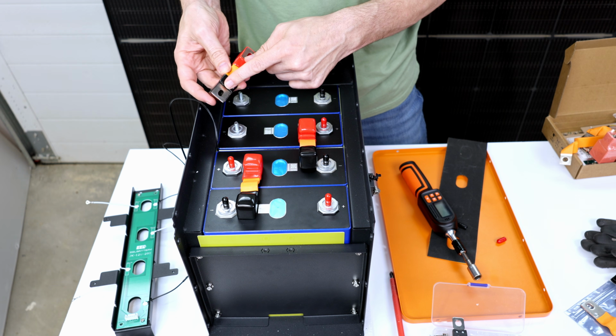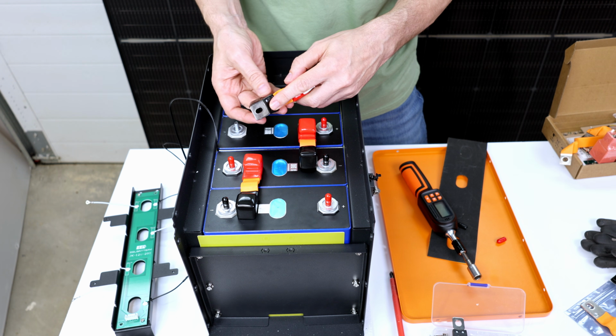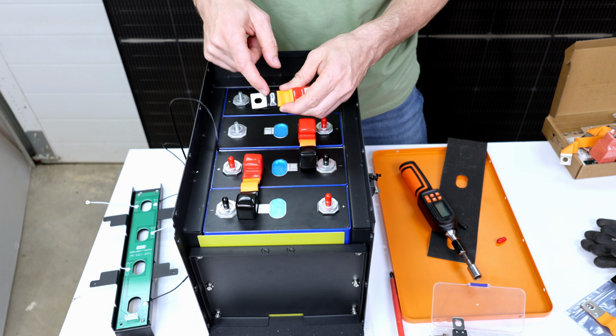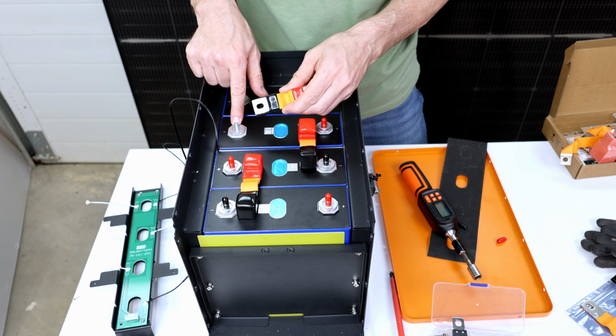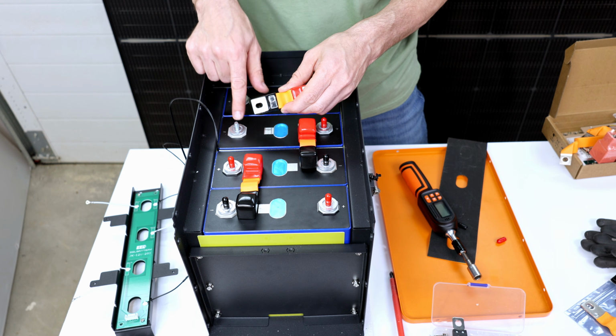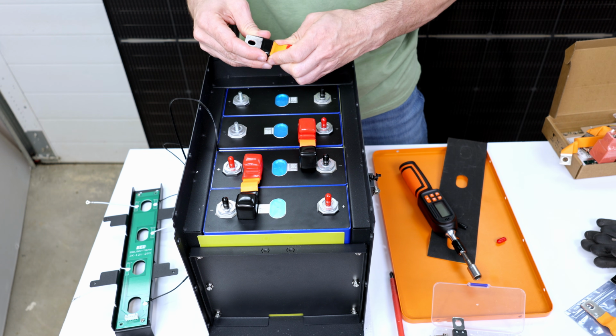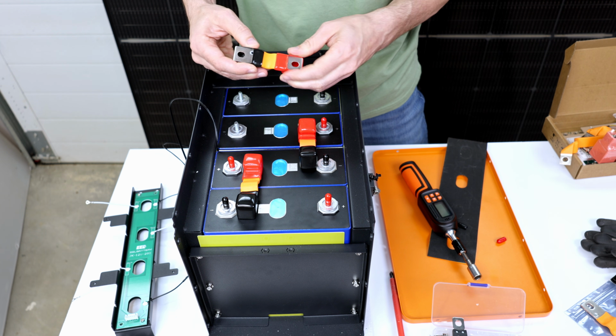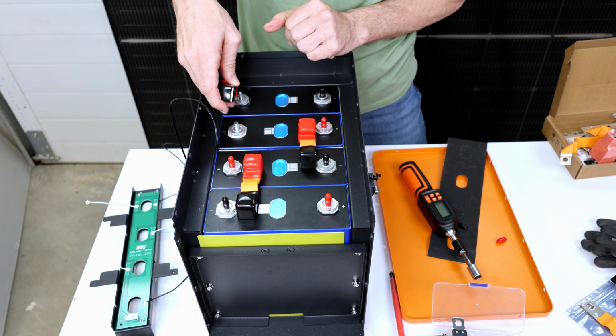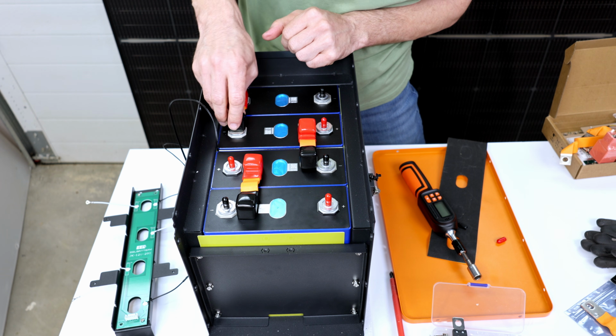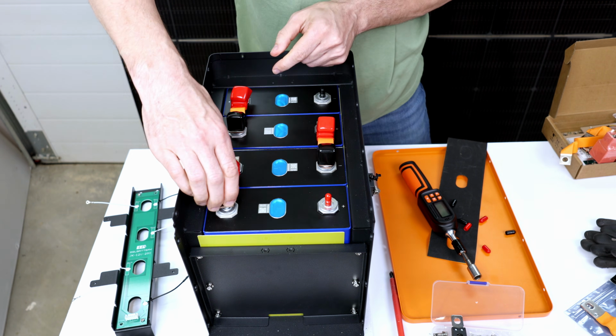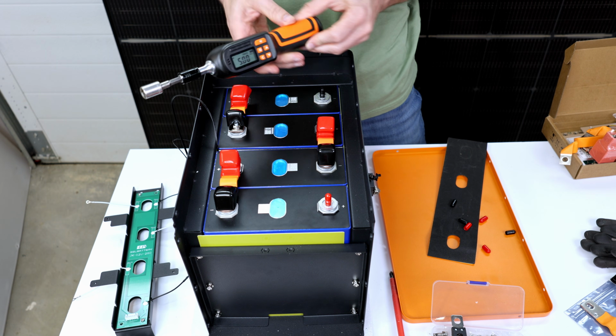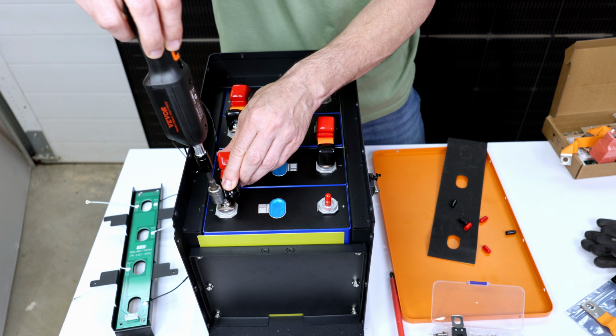Because these covers go underneath the bars, you'll want to make sure that you do not get any of this rubber under the contact surface for the lugs. So I'm going to push that back fairly far, make sure that I don't have any risk of contact there. All right, now my torque wrench is set to 5 Newton meters, and I can go ahead and torque these down.